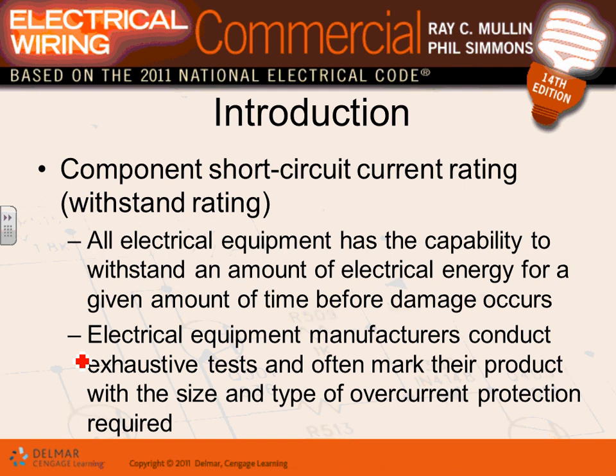Withstand rating is the most important term that you are going to hear about. All electrical equipment is labeled by the manufacturer with its withstand rating, meaning for 3 cycles, 5 cycles, it can handle this amount of power. So withstand rating is a function of how much current the equipment can handle and for how long. Energy: how much and for how long. It's not enough just how much, but for how long. That's why they call it electrical energy, for a given amount of time, before what happens? Before it explodes. That's withstanding.